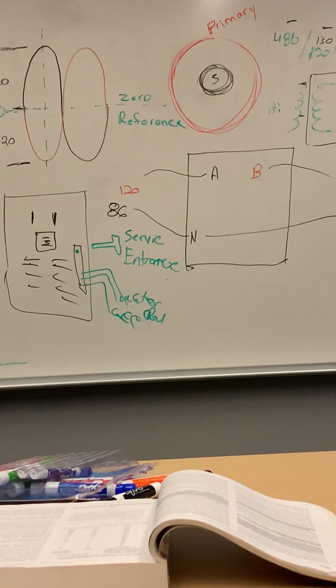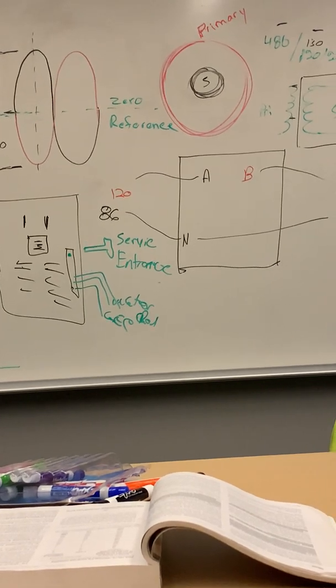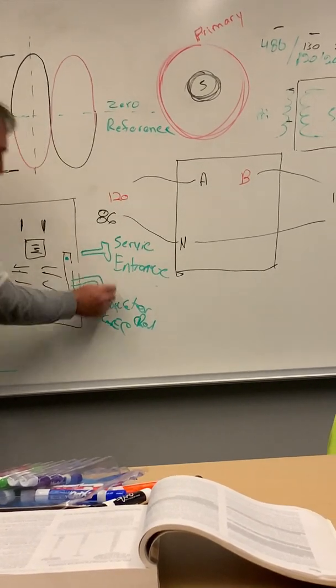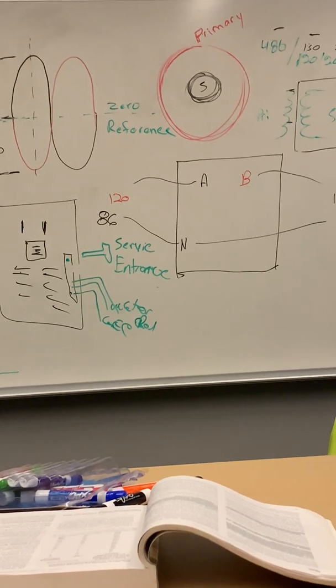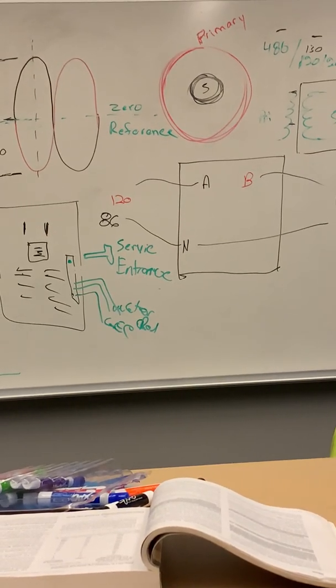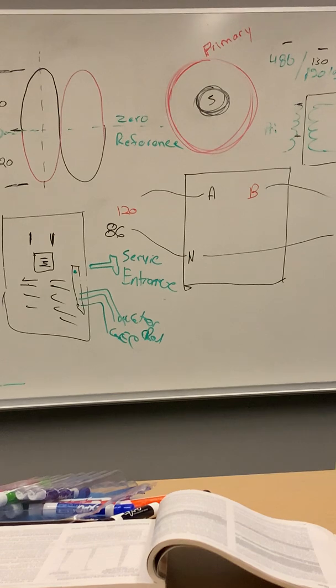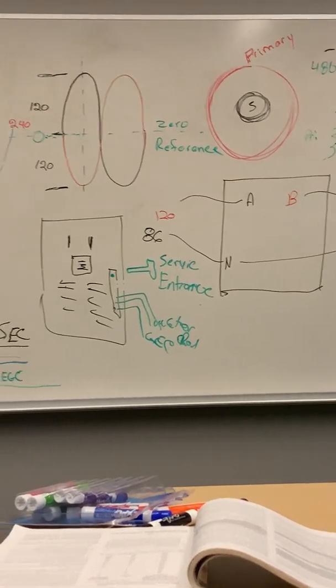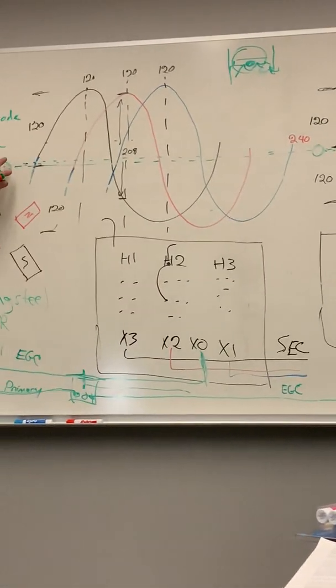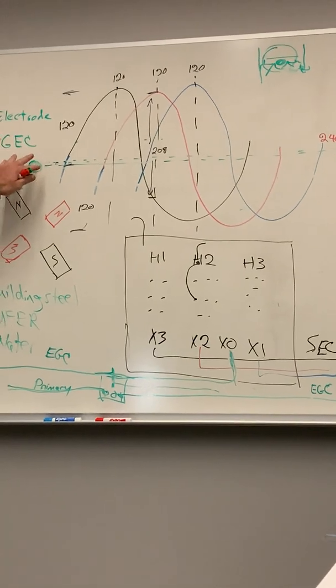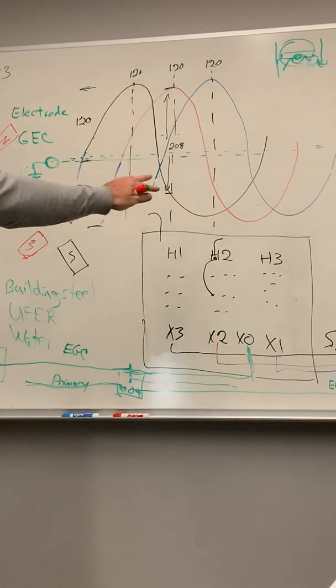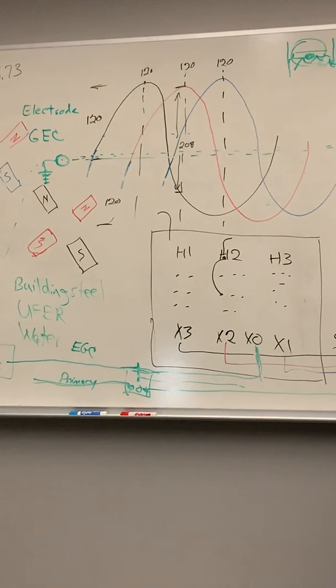But then also, if I had a white pen on this whiteboard, I could show you that neutrals are on there too. The service entrance is the only place. That's because we're creating this zero reference so that the neutral can be used as a zero reference, but also if there's a fault current, it will be brought back.